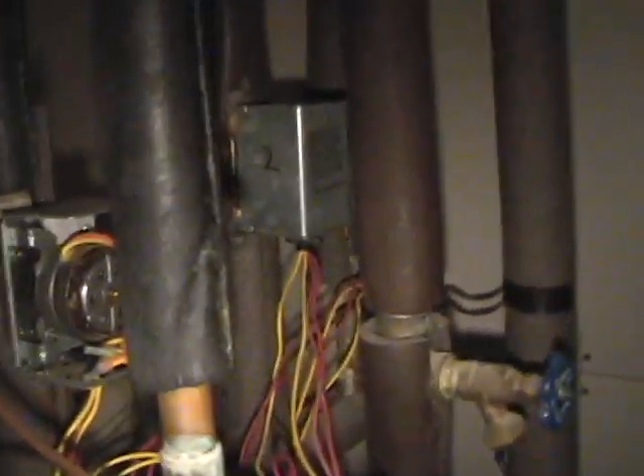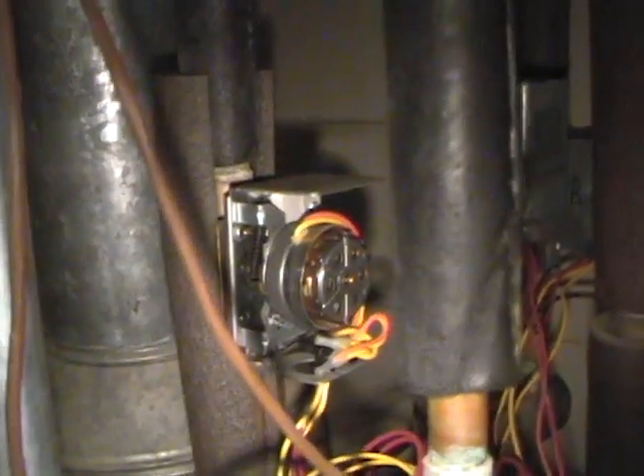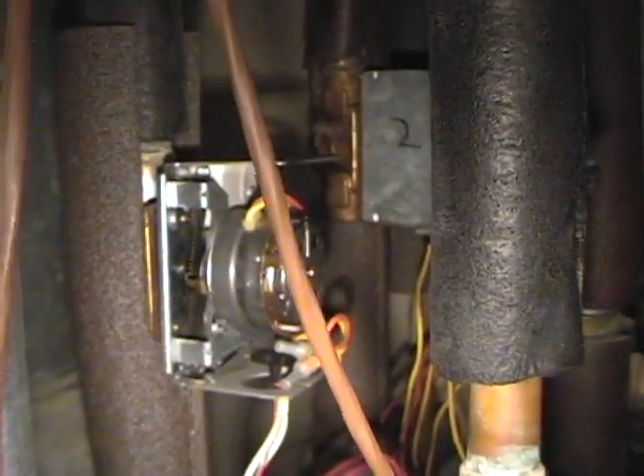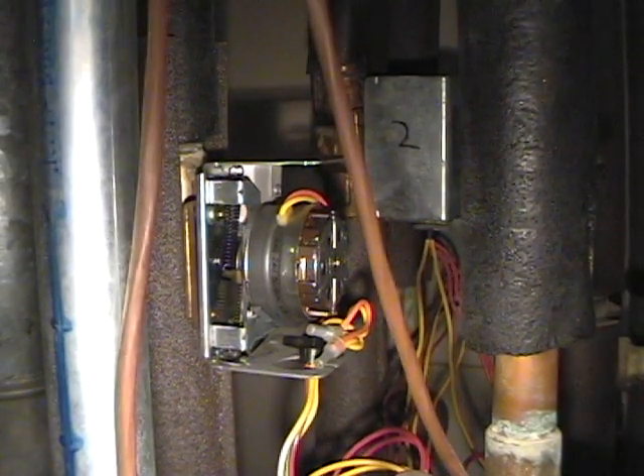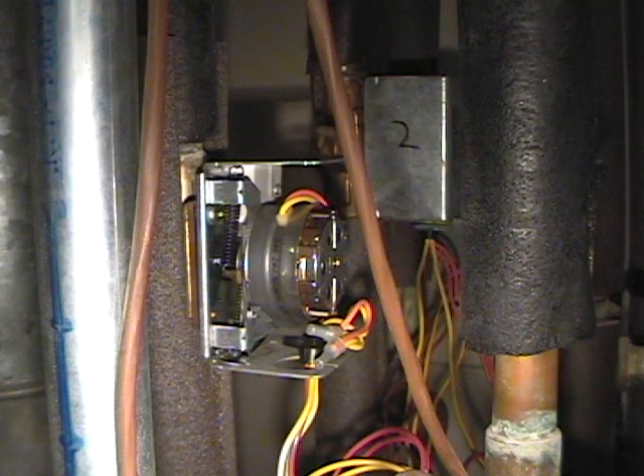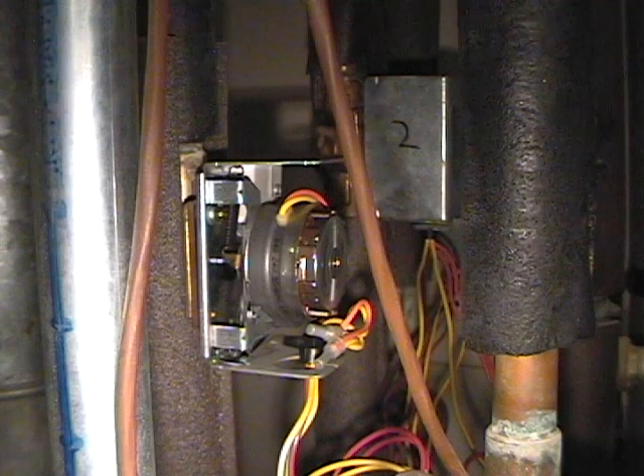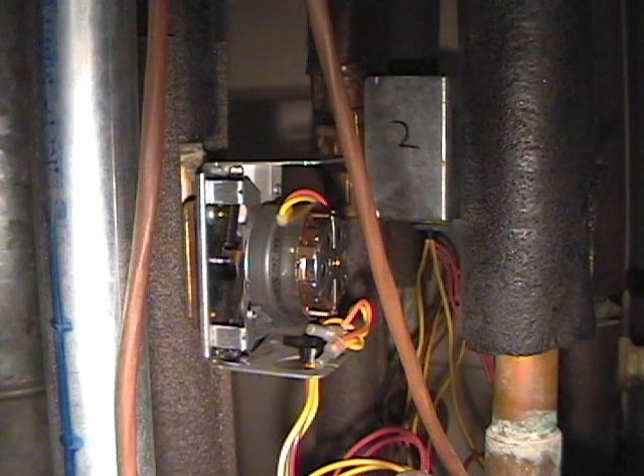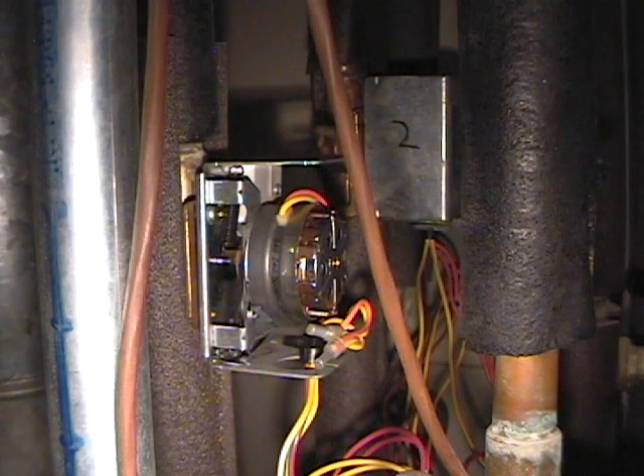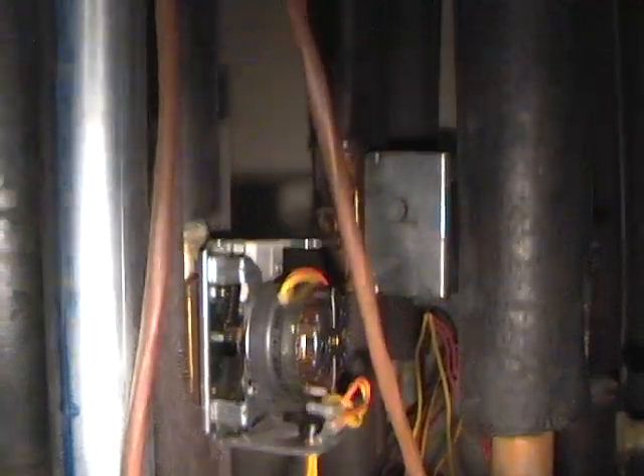And like I said, what you'll notice is when the valve closes, the disc will start spinning just seconds before it actually shuts off. So you can see that the valve does control the power. So I'll set the camera down and I'll go take care of that. Yep, and as you can see, the valve closed and power stopped soon after. So it's a pretty cool device, all mechanical, which you know me, I like.